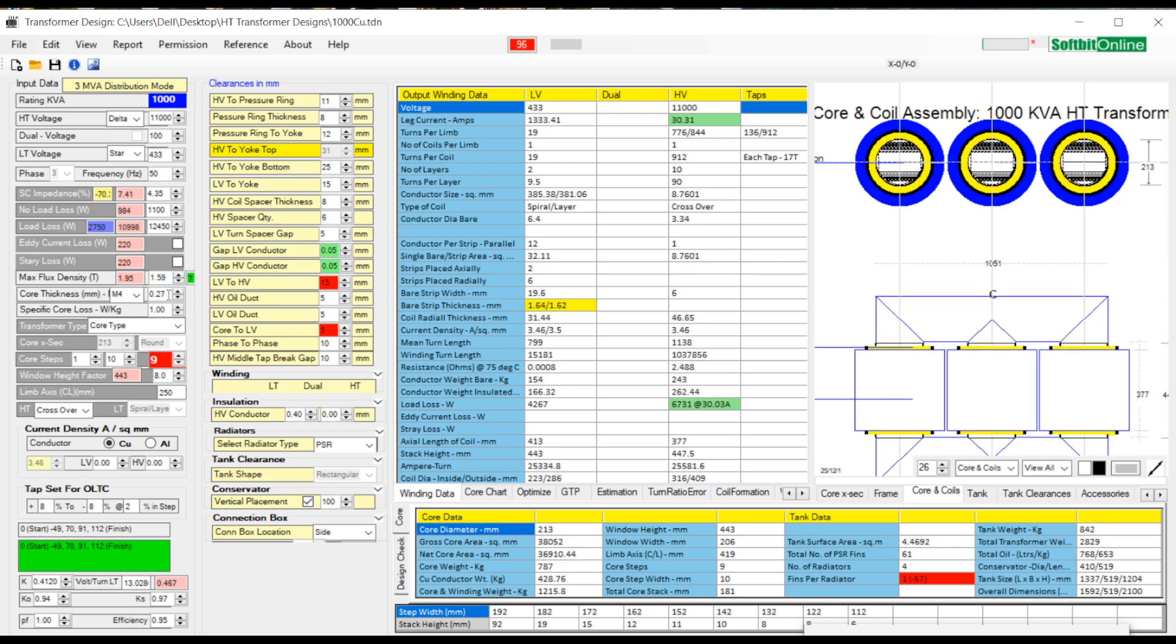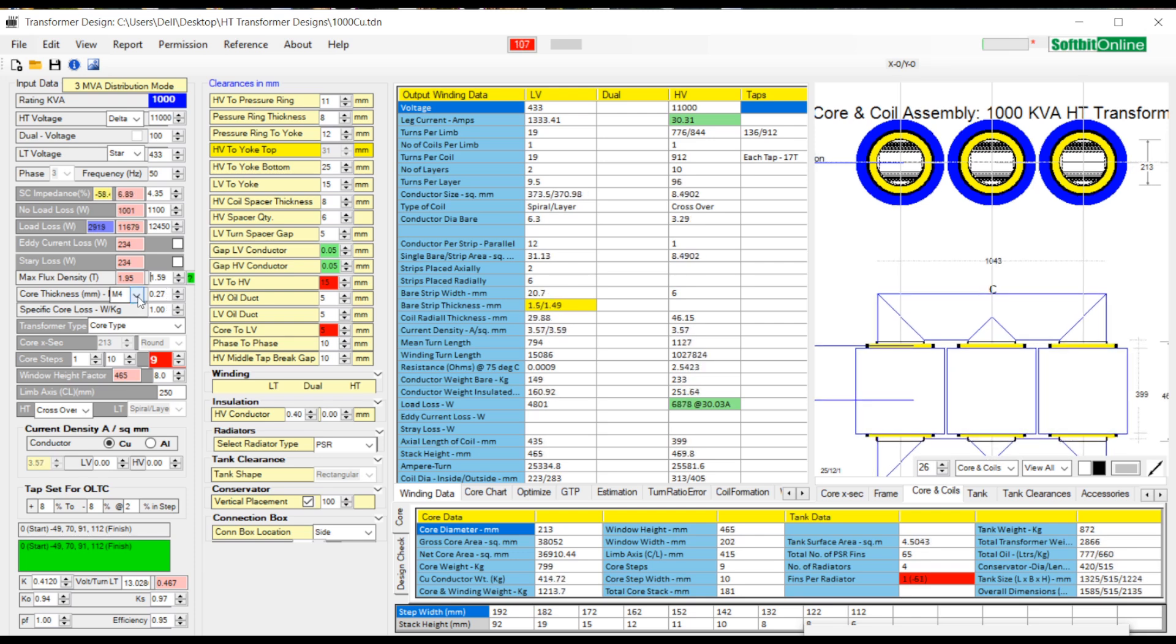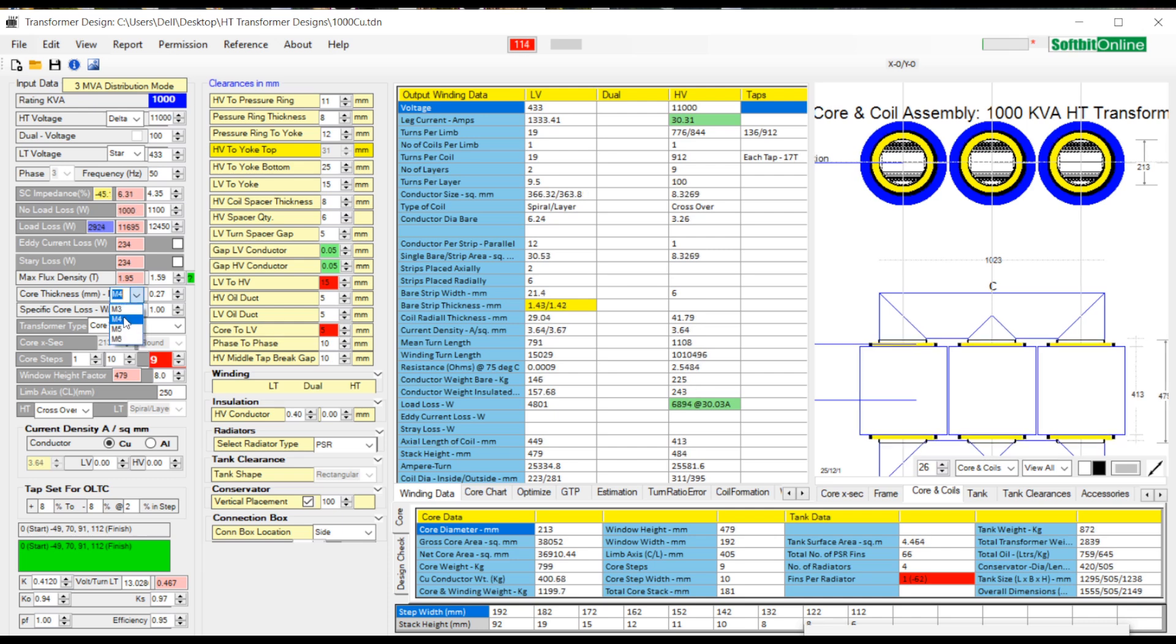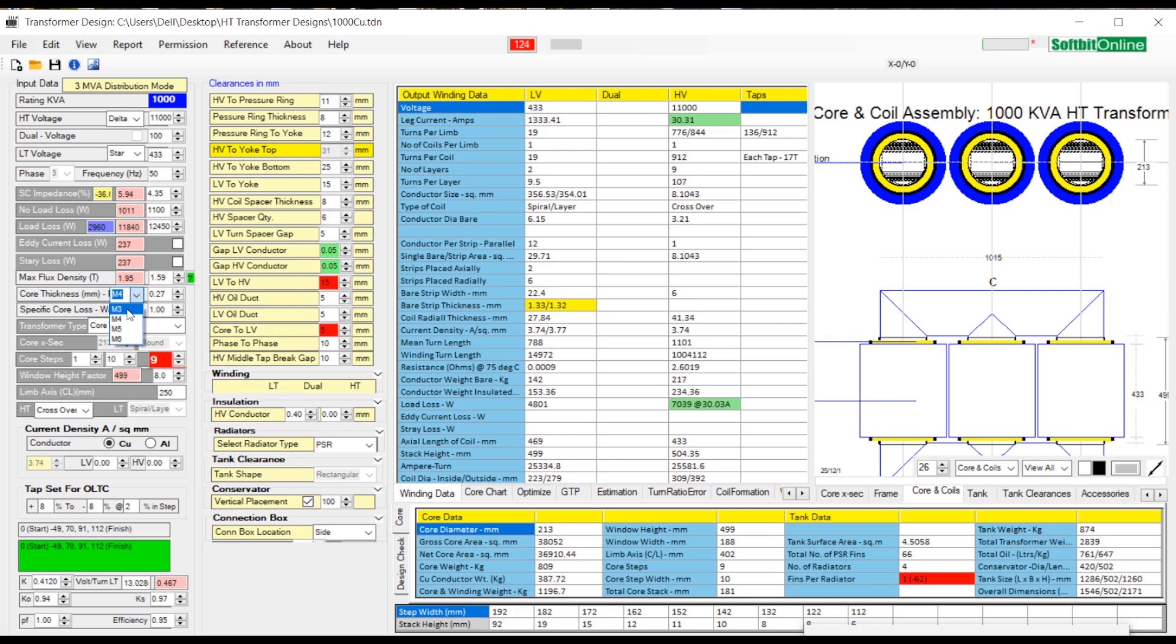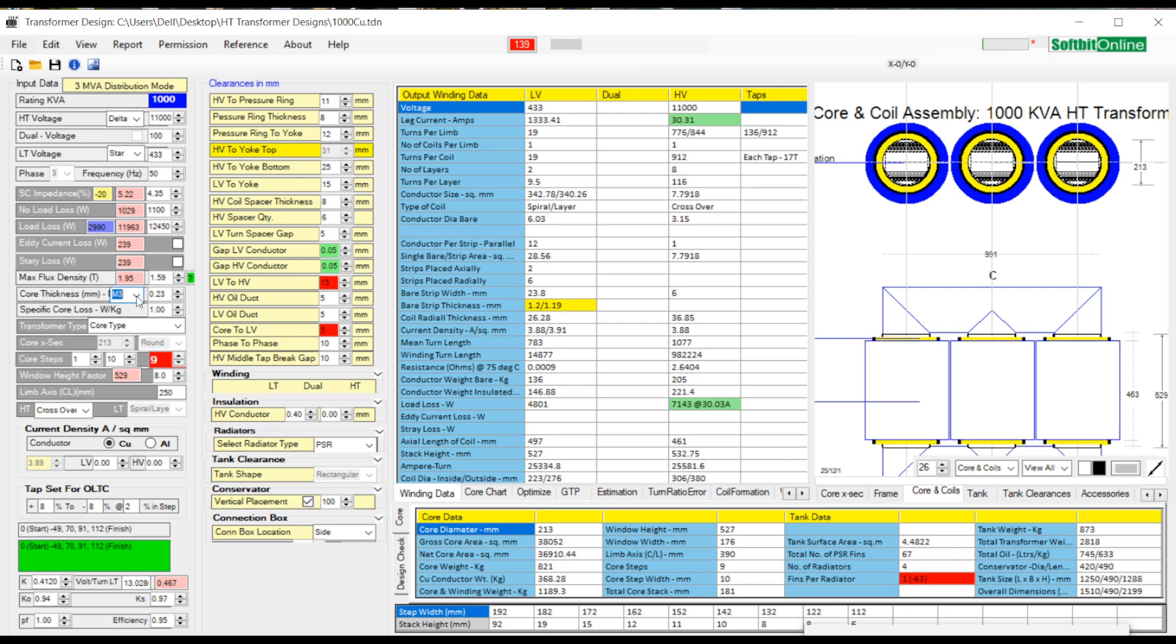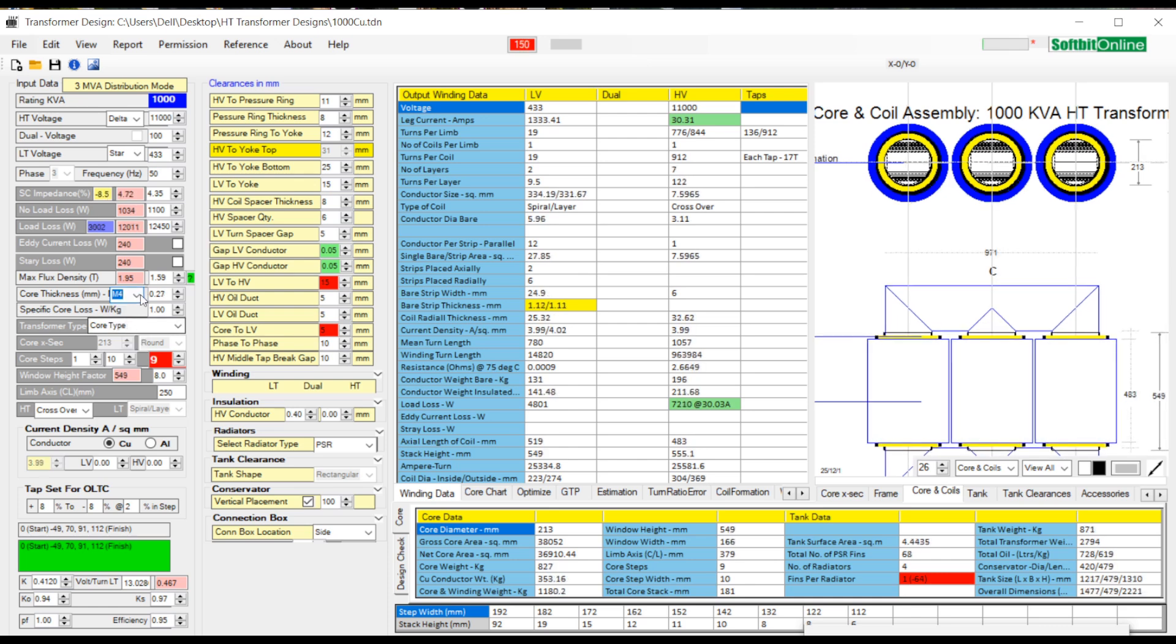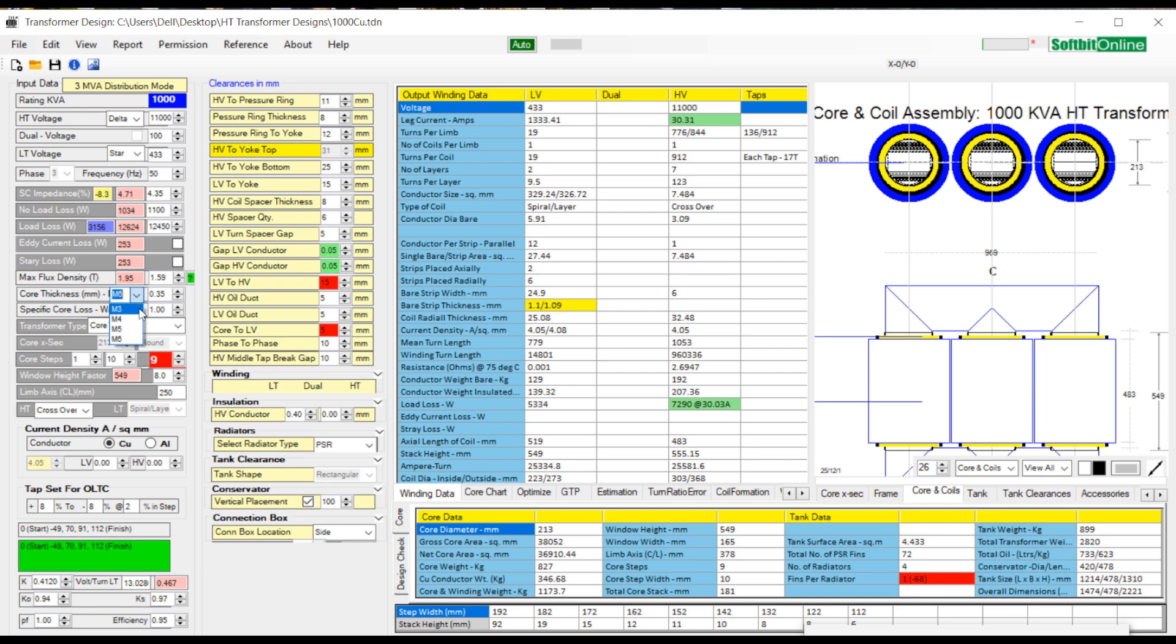Next comes core grade and lamination thickness. You can select from available core grades: M3, M4, M5 and M6. Corresponding thickness of lamination automatically changes. For grade M3 lamination thickness is 0.23 mm, for grade M4 the lamination thickness is 0.27 mm, for grade M5 the lamination thickness is 0.30 mm, and finally for grade M6 the lamination thickness is 0.35 mm.